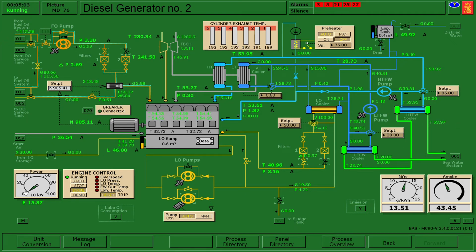Okay, so that is stable now. We're just gonna keep monitoring closely. Okay, there's an alarm. Acknowledge and then just silence. So to rectify the alarm, all we need to do is do a changeover. So to change over, we just need to close filter number 1 and open filter number 2.